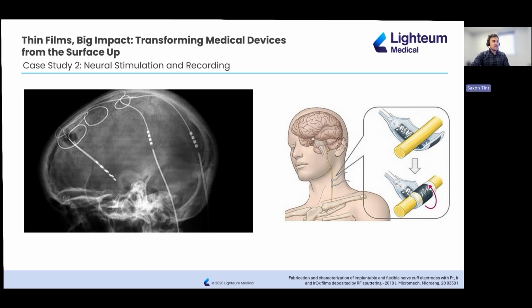So just look at where these electrodes are placed: in the brain, around peripheral nerves, along the vagus nerve. These devices are interacting with individual bundles of neurons in incredibly delicate tissue. What we're trying to record here is an extracellular action potential, the firing of a single neuron. And those signals are tiny, often around 100 microvolts. That's a very small signal sitting in a very noisy biological environment. To reliably record a single neuron firing, the electrode's geometric surface area needs to be extremely small, typically on the order of only a few thousand square microns, sometimes much less. If the electrode is too large, you stop seeing individual neurons and instead just record background neural noise. So we want very small electrodes.